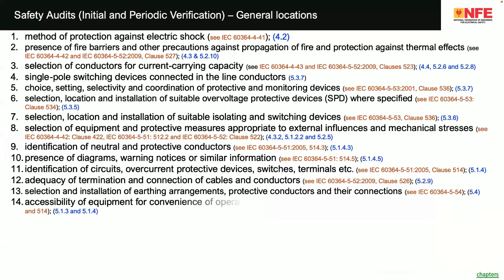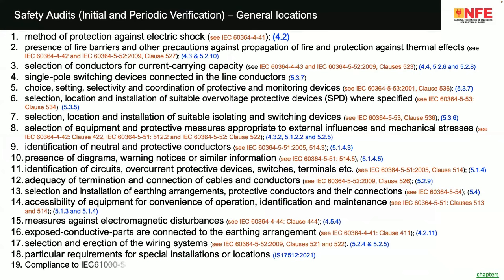This is another mess, I would say. Sorry to use the word mess, but it's a mess. The standards very clearly state what to do as verification. Verification consists of inspection and testing. Let me use the word generally used, audit. It consists of inspection and testing. Now, initial verification and periodic verification. Initial verification means before you use the building, before you use the transformer, before you use the panel board, before you use the wires, switches, sockets, you are supposed to make a verification consisting of inspection and testing.